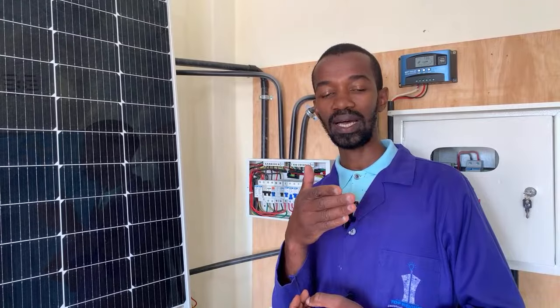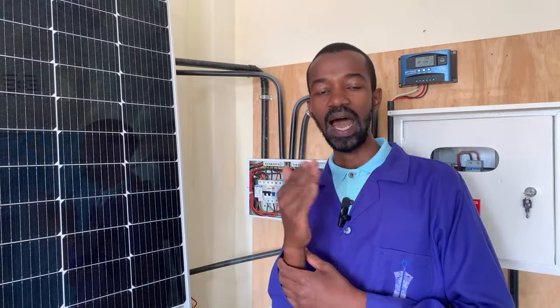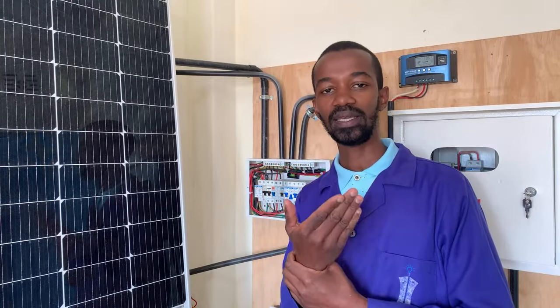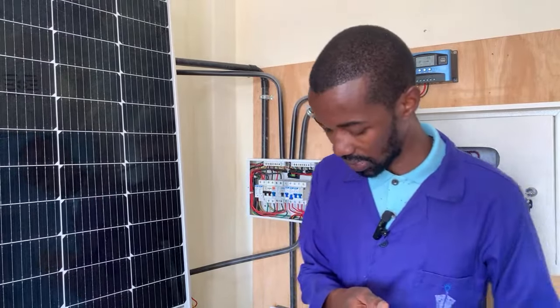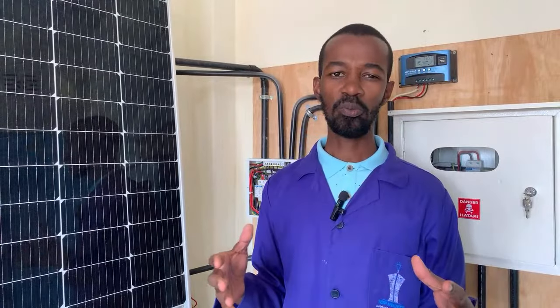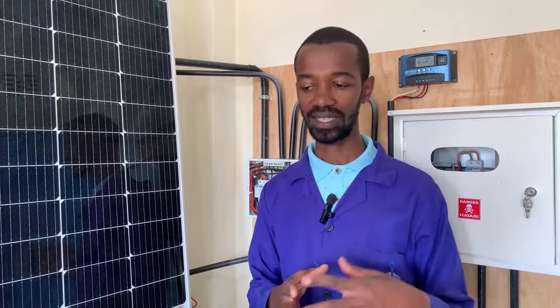When we are talking about a socket, we'll have a socket in the kitchen that is dedicated to a 32 ampere MCB. A socket in the bedroom or in the living room, which does not have high-powered appliances connected, we can have dedicated to a 20 ampere MCB. Then we will have other circuits such as the lighting circuit. A lighting circuit is dedicated to either a 5 ampere, a 3 ampere, or even a 6 ampere, depending on the load of that light circuit.